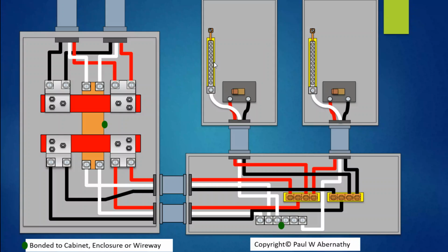And of course, here are your two main breakers for your two pieces of service equipment, and they have what's called a main bonding jumper in those. And if that main bonding jumper is a factory supplied main bonding jumper, then you do absolutely nothing. If it happens to be a wire that's making this connection, then you're going to have to size it, and you're going to size it based on the size of these conductors that are supplying this piece of equipment. All right, and again, we'll get into all those details here shortly.